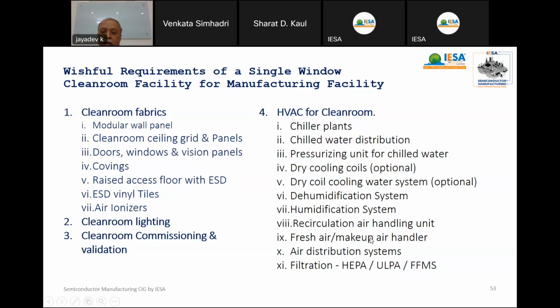Makeup air is also very important because normally makeup air is calculated based on the process exhaust taken out of the process tool. When you are exhausting, say, 5,000 CFM of air, I have to compensate 5,000 CFM of air from outside air. Apart from that, there may be a number of doors, and because the room is pressurized, a lot of exfiltration takes place. So the process exhaust plus exfiltration together, you calculate and make up properly for treated pressurized supply to the room.